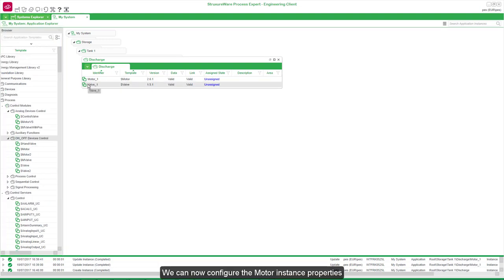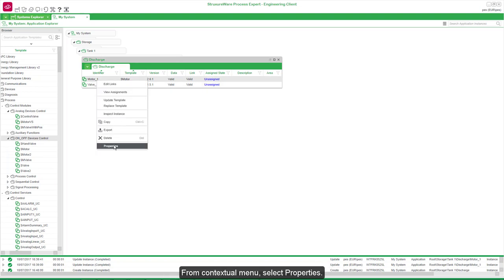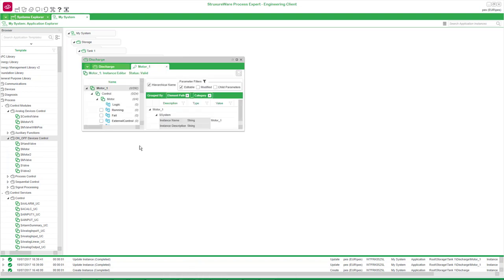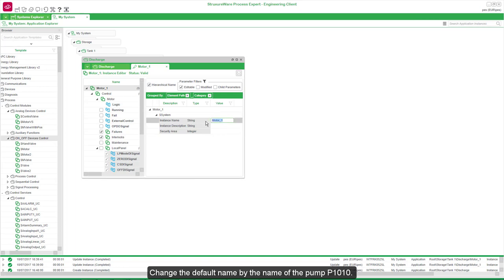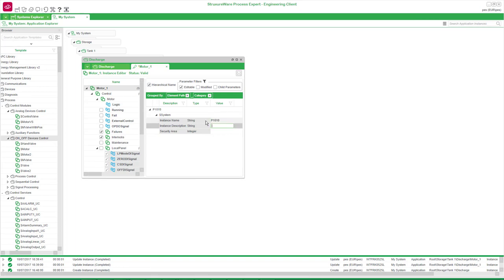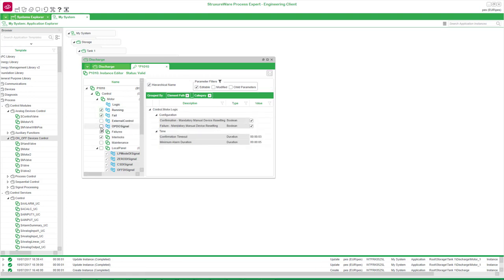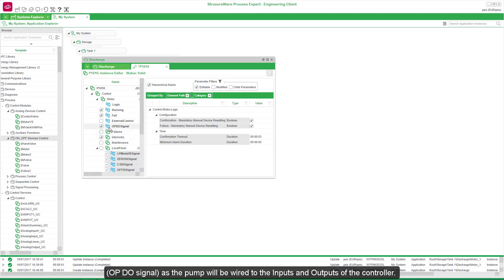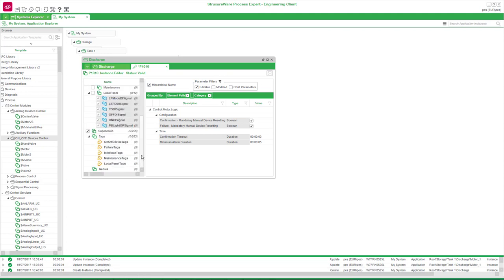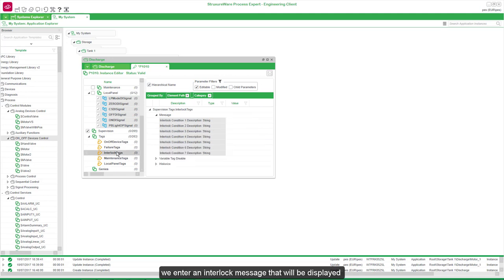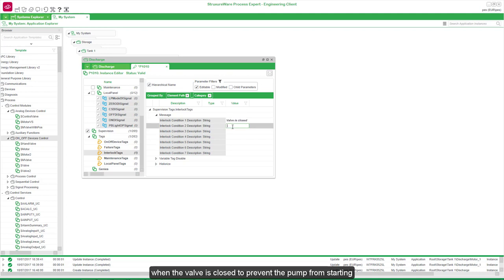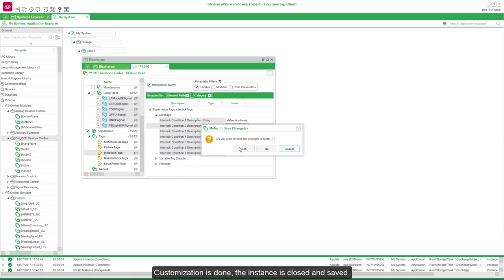We can now configure the motor instance properties. From the contextual menu, select Properties. Change the default name to the name of the pump, P1010. Enter a description and an area. We select the options Running, Fail, and OPDO signal, as the pump will be wired to the inputs and outputs of the controller. We enter an interlock message that will be displayed when the valve is closed, to prevent the pump from starting. Customization is done; the instance is closed and saved.